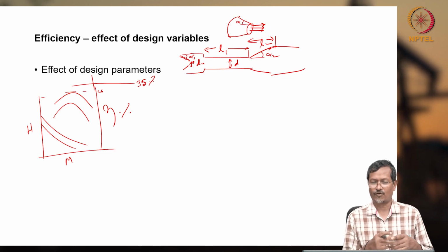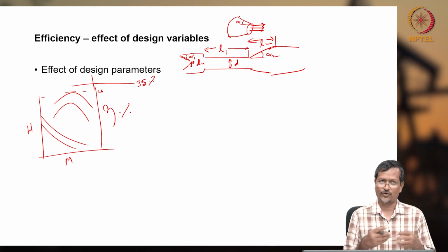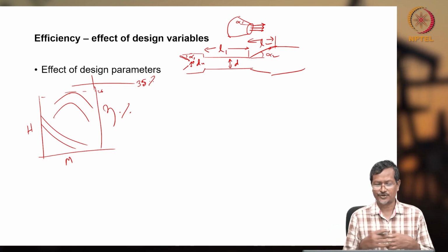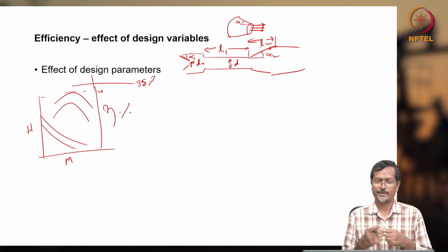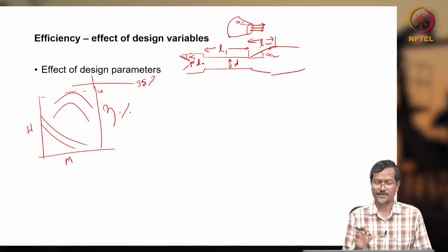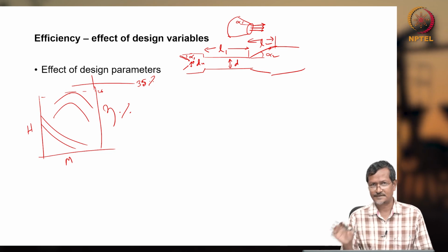This is optimal for all the parameters, all the designs, all viscosity, temperature, flow rate and pressure. There is no such jet pump. So for a specific application, there will be some optimal design. For example, high viscosity fluid or sand is there, gas is there.